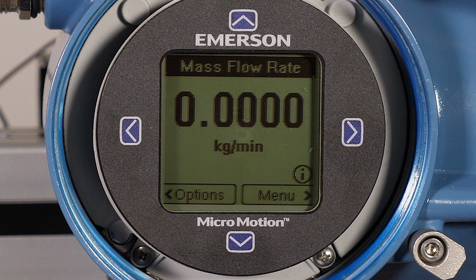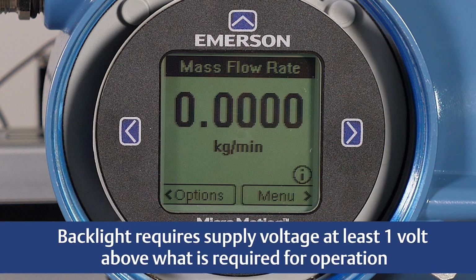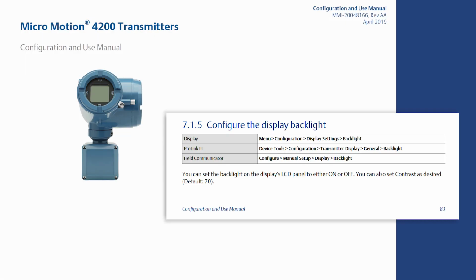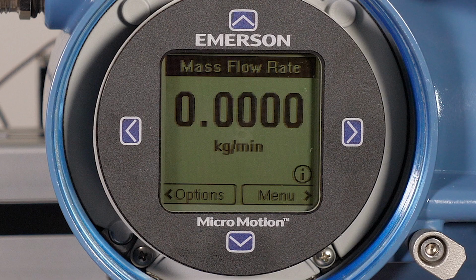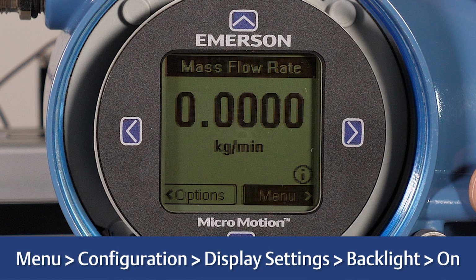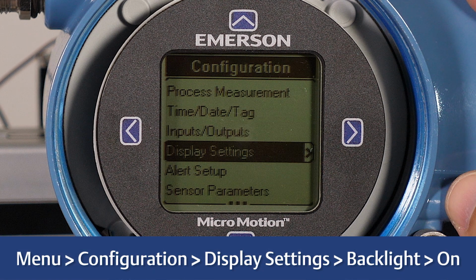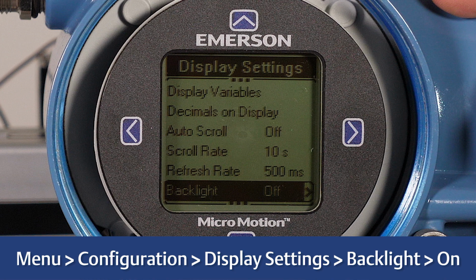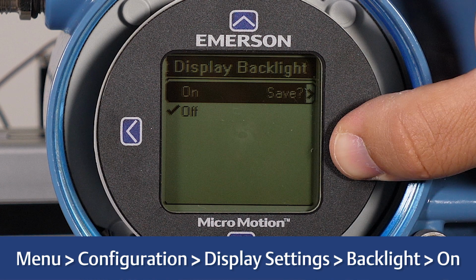The 4200 transmitter has an optional backlight feature. The backlight requires supply voltage at least 1 volt above what is required for operation. See the detailed information in the configuration and use manual. To turn on the backlight using the display, select Menu, Configuration, Display Settings, Backlight, On. Then, select and hold the right arrow key to save this configuration.